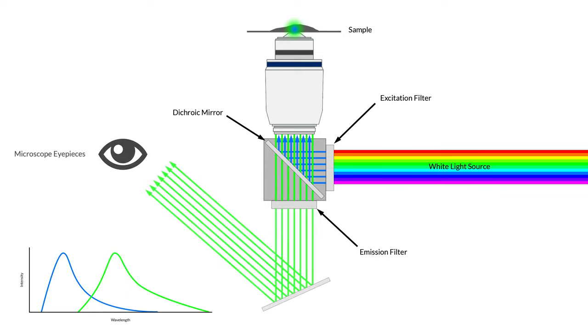This longer wavelength emission light is collected by the objective and makes its way back to the dichroic. Now because the range of the signal emitted is longer than 500 nanometers, it will transmit directly through. Once the emission light transmits through the dichroic, it will encounter an emission filter, which much like the excitation filter is a bandpass filter. The emission light is then directed to the eyepieces of the microscope or even to a camera to detect the fluorescence image.